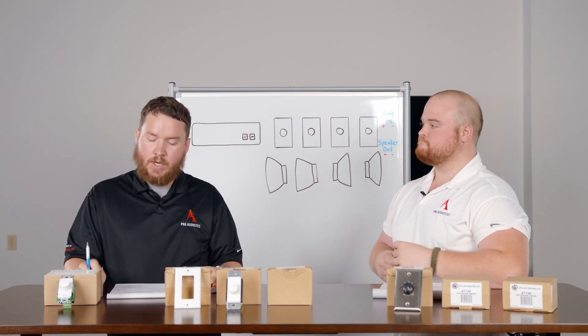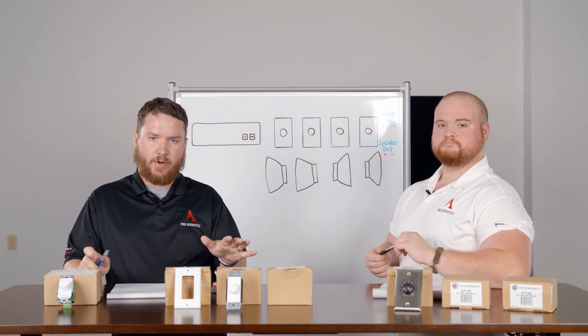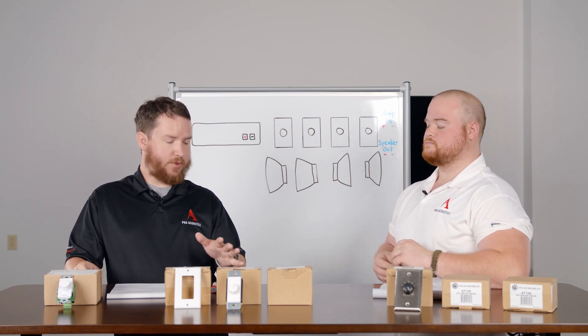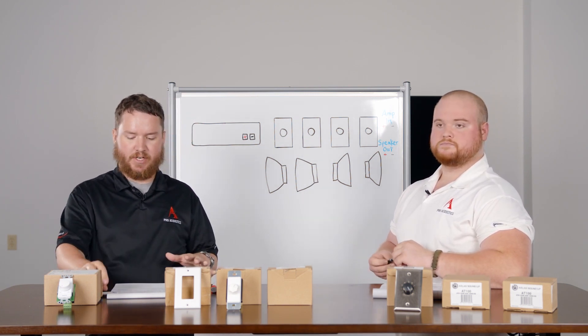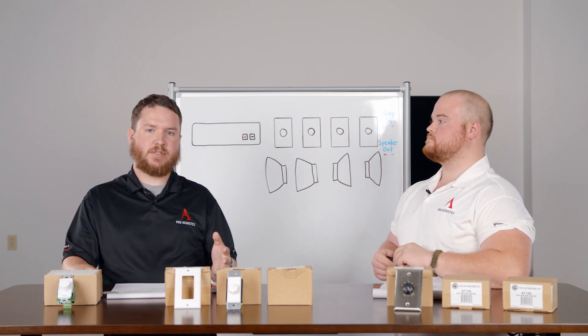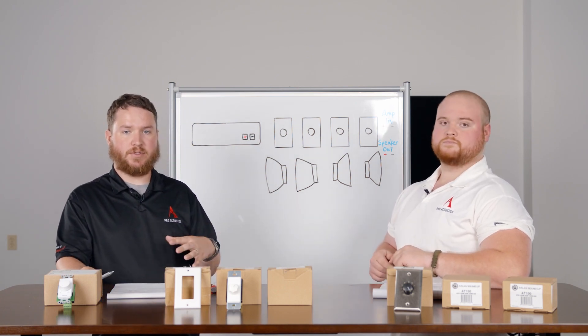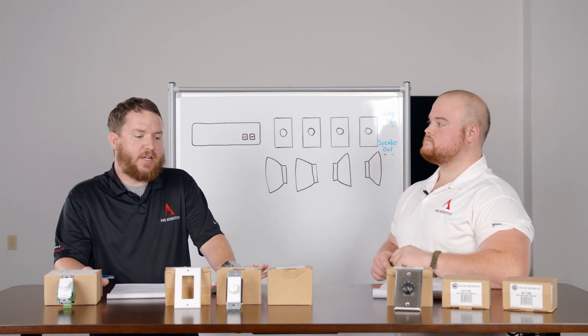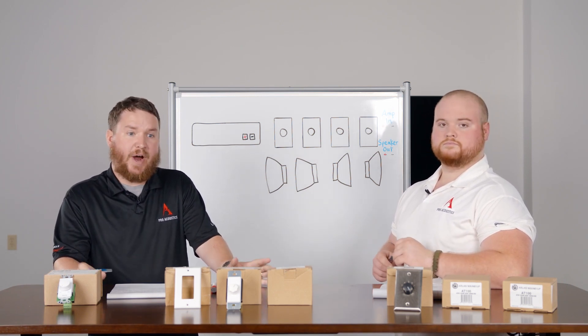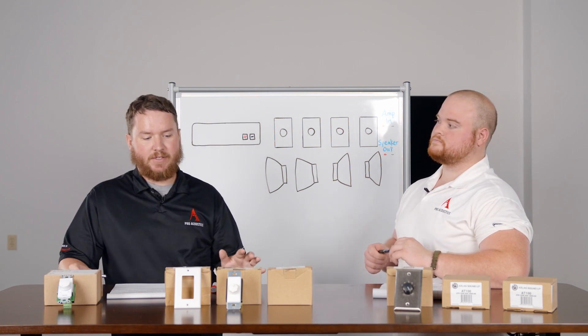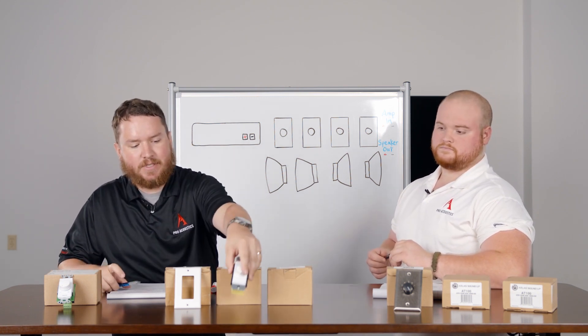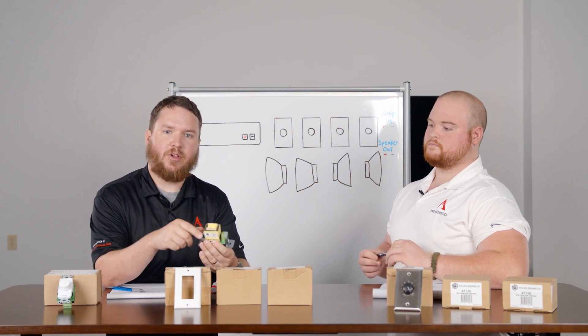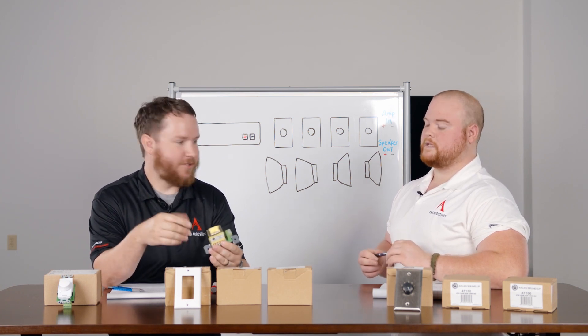So real quick, there are 8 ohm volume controls and then also 70 volt volume controls. 8 ohm volume controls tend to be used in home audio applications. For more info on home audio versus commercial, check out one of our other videos. But we're talking all about 70 volt volume controls here. Why does it matter? It matters because there is a transformer on the back of some of these volume controls, actually almost all of them. And the electrical voltage matters.